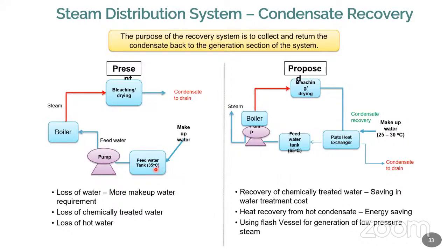Earlier you had 35 and the maximum temperature is 100. So 100 minus 35, into Cp equal to 1 because it's water, into the amount of mass required to heat the water to produce the steam fuel. Now it is 65, so 100 minus 65. Therefore the mass value will reduce. So this will be a huge saving for us.